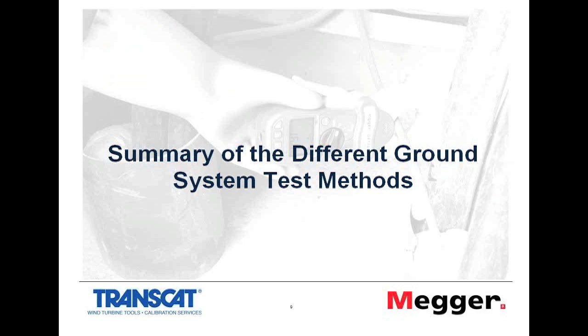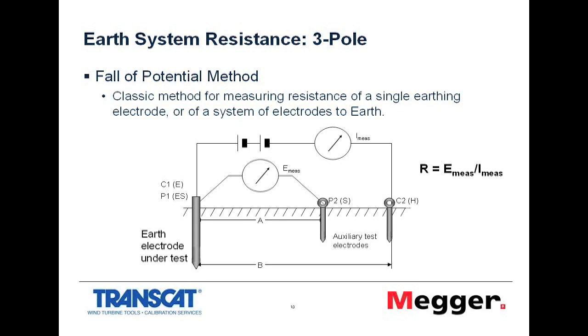We had a quick discussion there about the clamp, but reverting back to the 3-pole methods, there are a number of methods for doing this. The most common and the most traditional method is the Fall of Potential method. As I mentioned earlier on, we're going to put an auxiliary probe in the ground to inject a current. We're going to place an auxiliary potential or voltage probe to measure the volt drop across the earth mass. And then we're going to calculate the resistance simply by taking the voltage and dividing it by the current.